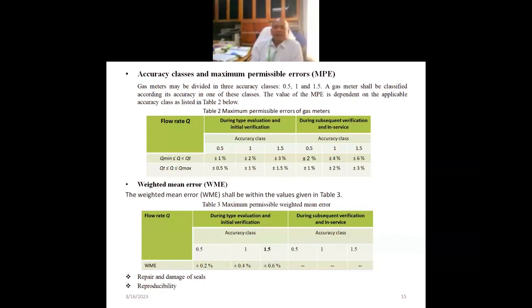First, during the type evaluation and initial verification, error for accuracy class 0.5 is plus minus 1%, and for accuracy class 1, it is plus minus 2%, and for accuracy class 1.5, it is plus minus 3%. It is during the evaluation and the initial verification. And when the Q transitional flow rate is less than or equal to flow rate Q is less than or equal to maximum flow rate, for accuracy class 0.5, the initial maximum permissible error is plus minus 0.5%, and for class 1 instrument it is plus minus 1%, and for class 1.5 it is plus minus 1.5%.